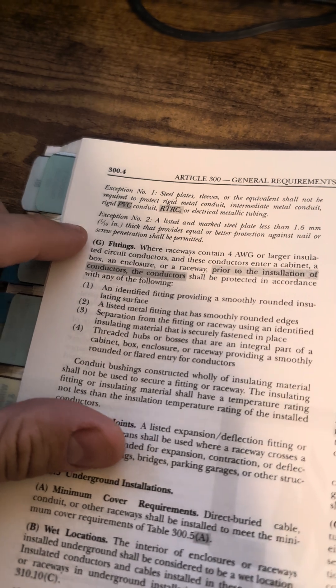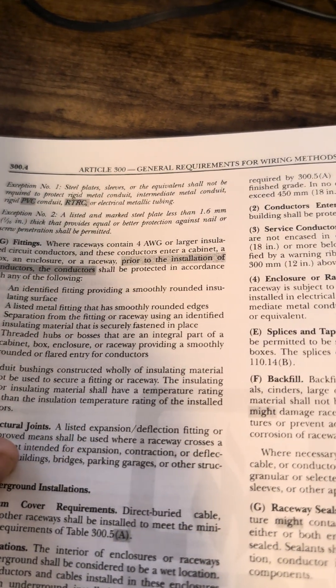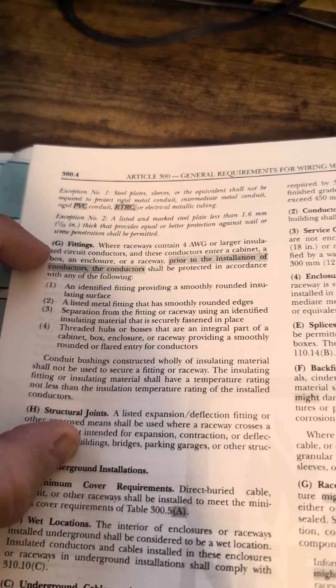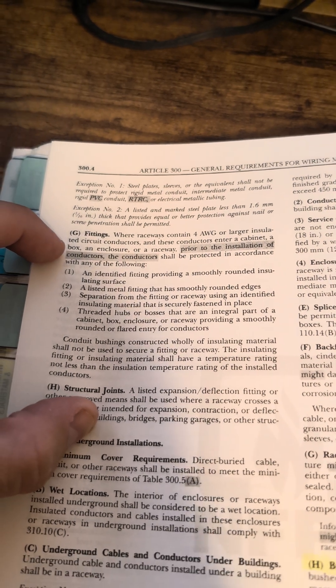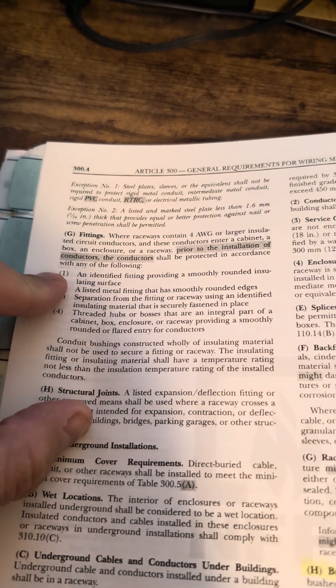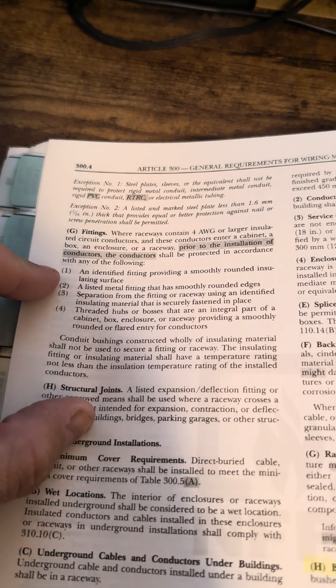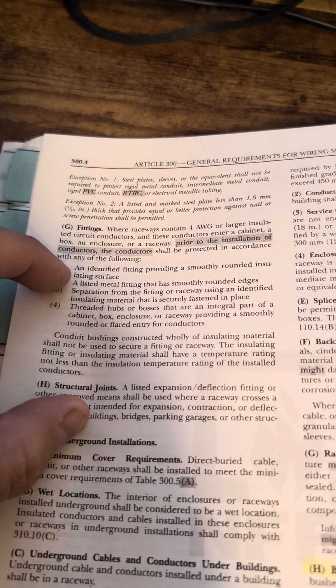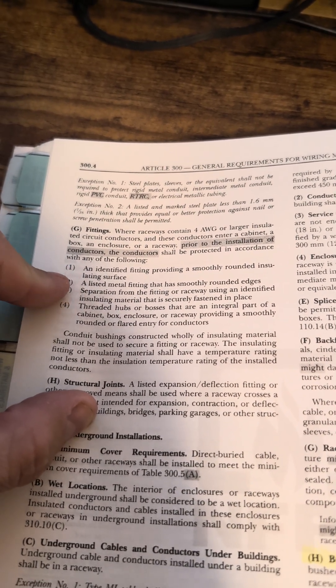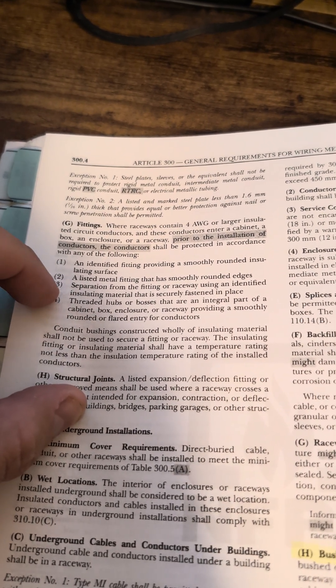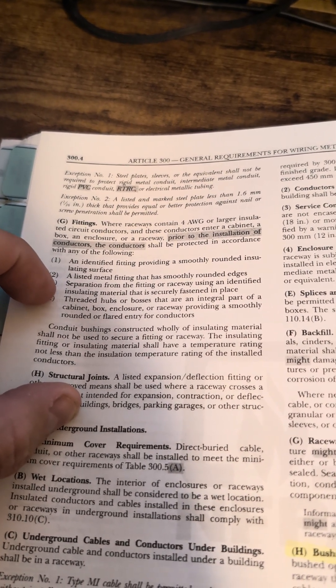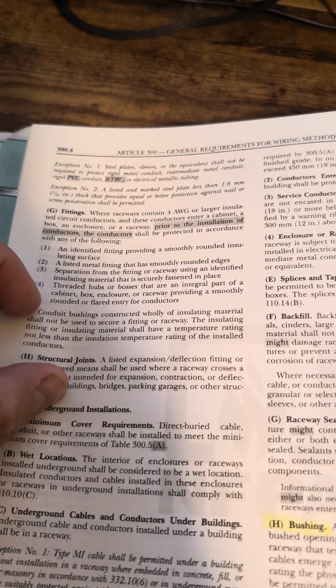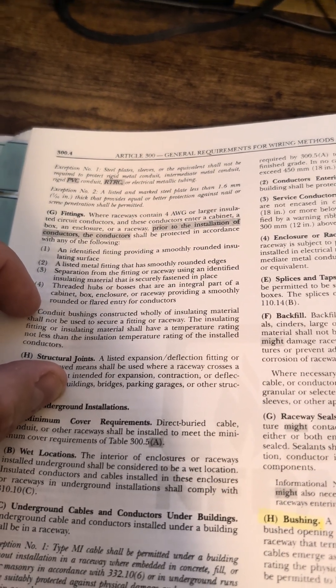Fittings. So when a raceway for larger insulated circuit conductors, so it specifically says insulated, enters a cabinet, shall be protected in accordance with any of the following: an identified fitting, a smoothly rounded insulating surface, a metal fitting that has smooth rounded edges, separation for the fitting and raceway with an insulating material, or threaded hubs or bosses integral part.